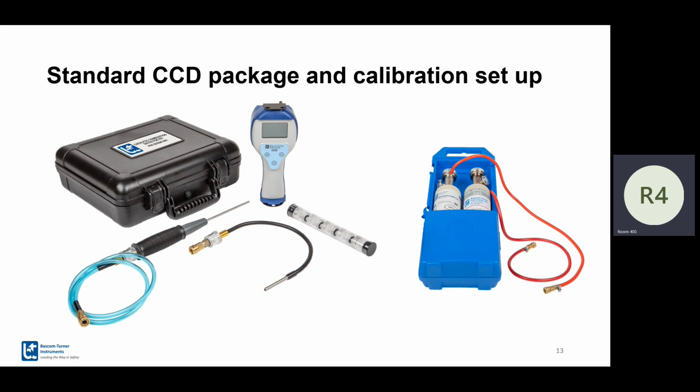Again, it's our interpretation of Method 21. There is no specific instrument that is approved for Method 21. Our technology meets all the requirements and then some. There might be site-specific requirements that it does not meet because the site might require an FID. There may be some consent decrees. But we have done a series of crosswalks with section 6.1 and our technology exceeds the requirements of Method 21, section 6.1 by more than a little bit in all nine plus categories. What does it weigh? 1.5 pounds.